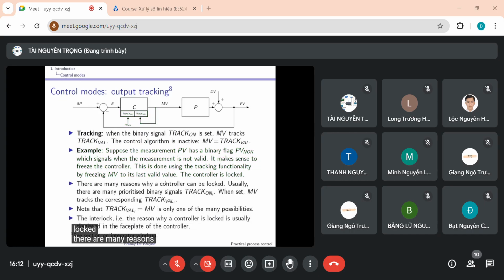There are many reasons why a controller can be locked, so usually there will not be one track on binary signal, but several of them. So there will be several track on binary signals with corresponding track value. Track number 1, for instance, has priority over track number 2, which has priority over track number 3. So if several of the track on are set to 1, MV will follow the activated track value with the highest priority.